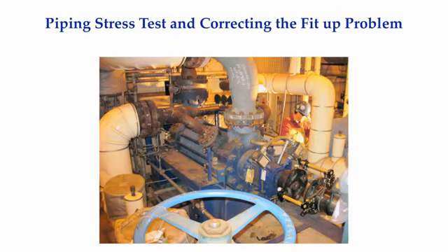Here's a multi-stage pump where we did the static piping stress test in reverse. After the unit had been offline for over a week, we attached some brackets on the motor shaft and placed indicators on the pump shaft. We also set up some magnetic bases and indicators to monitor any lateral movement at the bolting planes. When we loosened the inboard bolts, the pump raised up about 20 mils at the coupling.